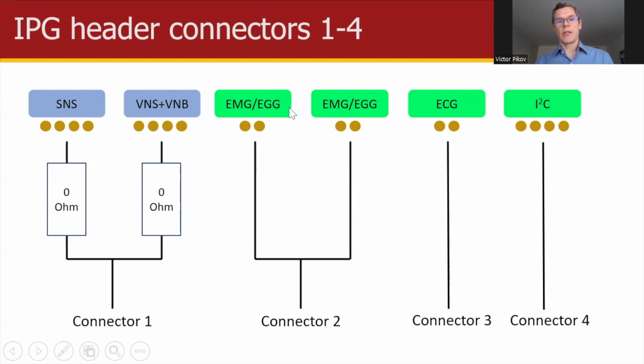For EMG and EGG, our idea is we have 2 channels, and again, based on the filter settings, we select either EMG or EGG. And since it's only using 2 contacts, we can actually have 2 leads using the same contact, and then it will split using the kind of splitter that was described earlier to connect 2 of these leads to a single connector. EKG will have its own connector because it's quite important for a lot of autonomic applications, because we can detect both the heart rate and respiratory rate, and the heart rate can be used for deciphering information about sympathetic and parasympathetic activity, which is key for tuning the therapy.